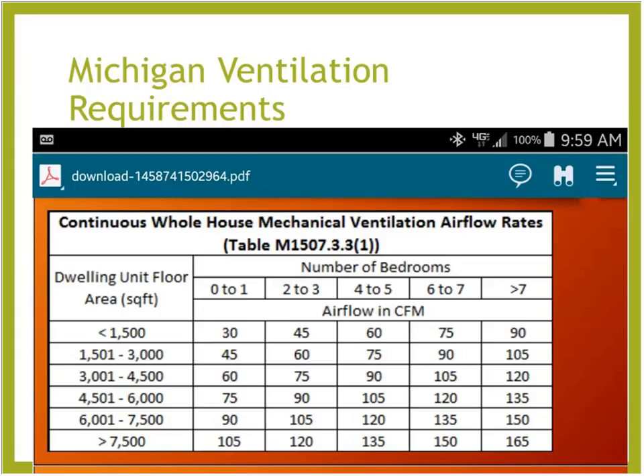So when we go to verify those flows for these above grade programs, we'll use a flow hood or some pressure pan system that we can measure those with, and we'll find that they're woefully inadequate for the ventilation requirements or fresh air requirements of that system. Yeah, that's been our results as well. We've actually taken flow stations, put them in line, and I think the top test was like 37 CFM coming in through a 6-inch scuttle, and that was pretty close to the furnace, where the negative pressure in the cold air return is going to be pretty high, or higher than it would be further down the line, because as you mentioned, where they install it, how they install it has just a huge impact as well.